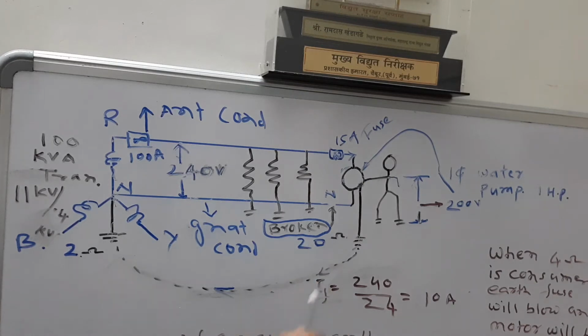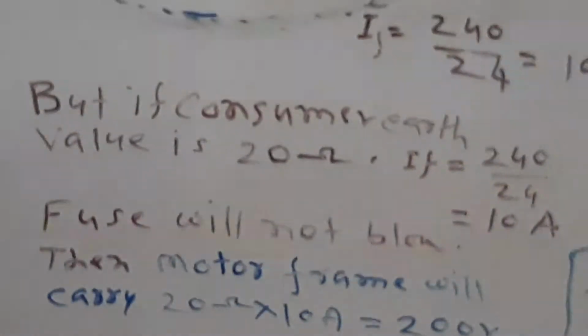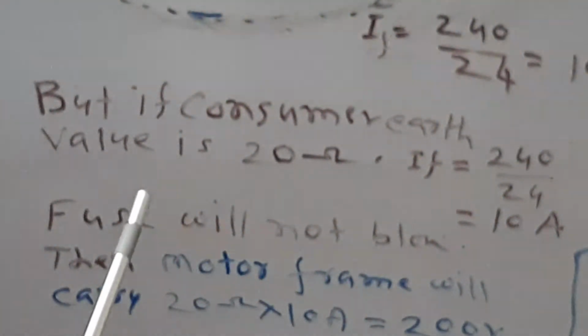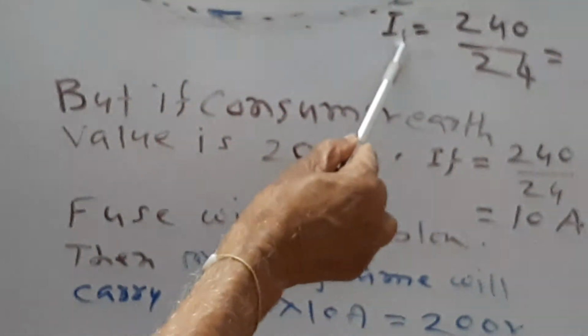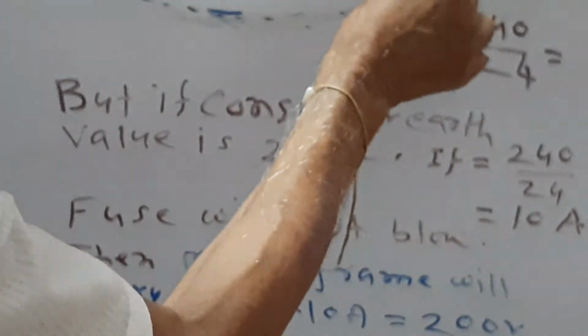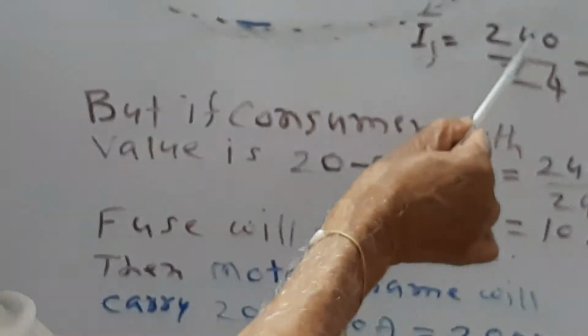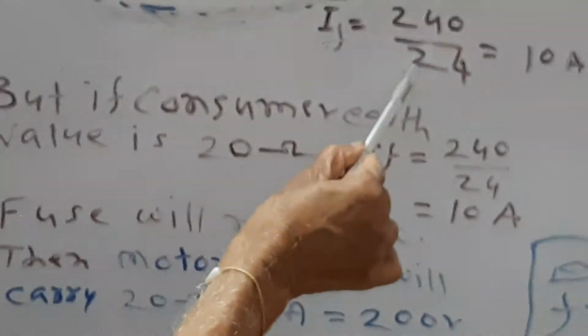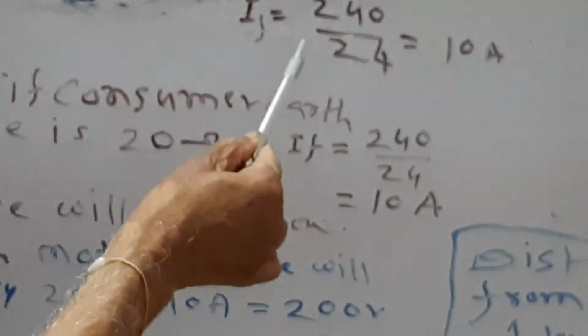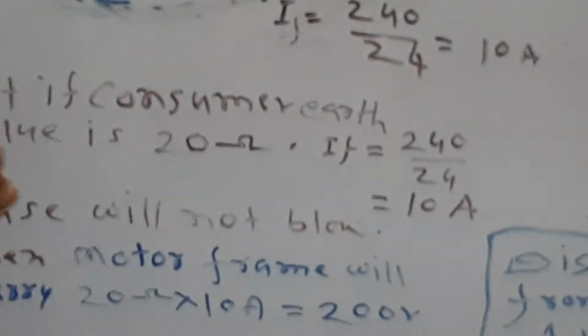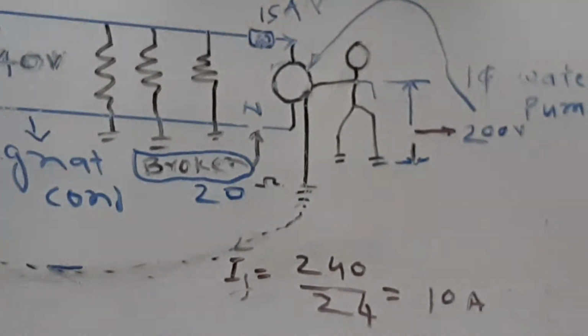Now, I will show you the calculation. Kindly see. Now, if we calculate the value of this fault current, meaning the current flowing from the frame to this neutral, IF is equal to 240. 240 means the voltage across the motor, and 24 means the consumer earth value of 20 ohm plus the neutral, which should be 4 ohm, not 2. So this will be 240 divided by 24, that is 10 ampere.